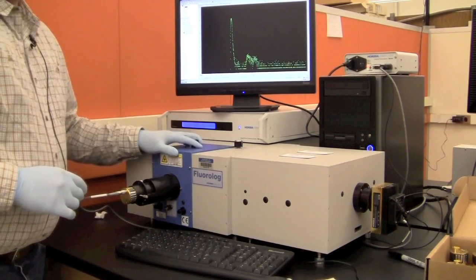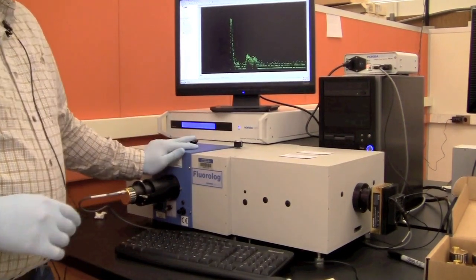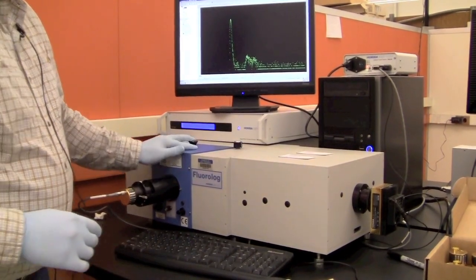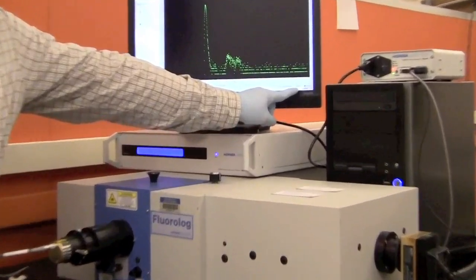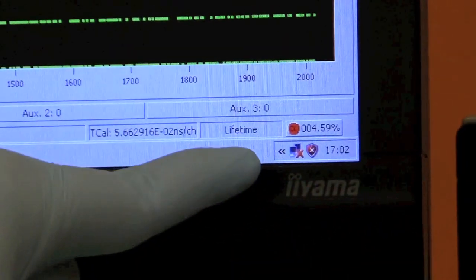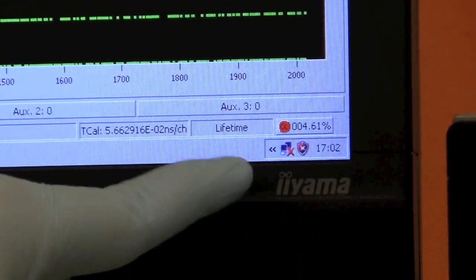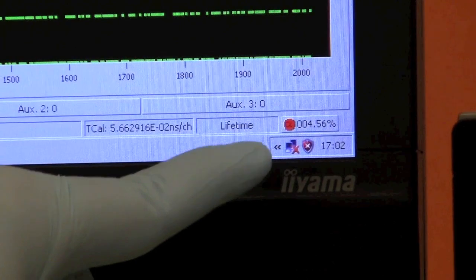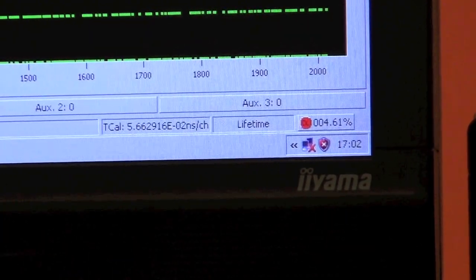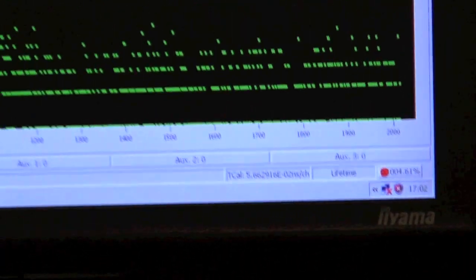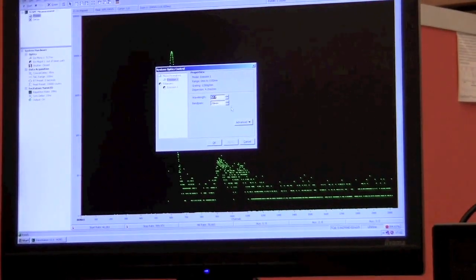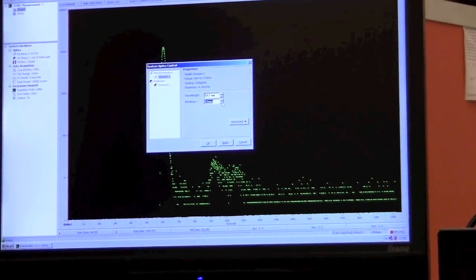Now that I have my sample in, I have to make sure I'm counting enough photons. You can see on the lower right-hand side of the screen that green icon turned red, telling me there are too many photons being detected. So I need to close my slit width. I'm going to cut it in half.